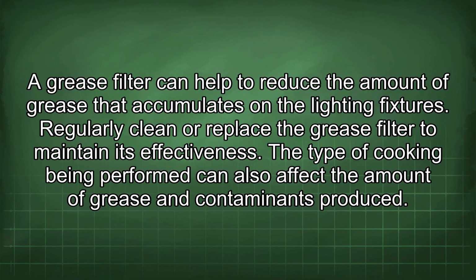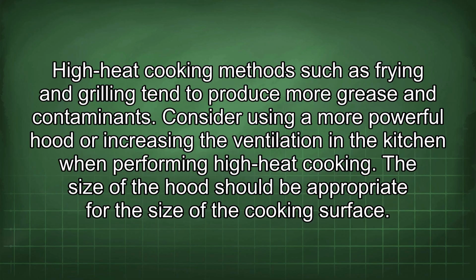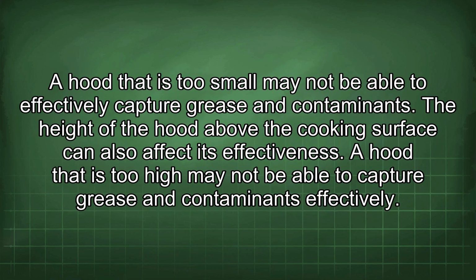The type of cooking being performed can also affect the amount of grease and contaminants produced. High heat cooking methods such as frying and grilling tend to produce more grease and contaminants. Consider using a more powerful hood or increasing the ventilation in the kitchen when performing high heat cooking. The size of the hood should be appropriate for the size of the cooking surface. A hood that is too small may not be able to effectively capture grease and contaminants. The height of the hood above the cooking surface can also affect its effectiveness.